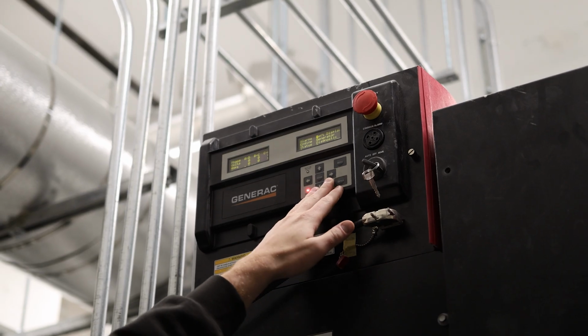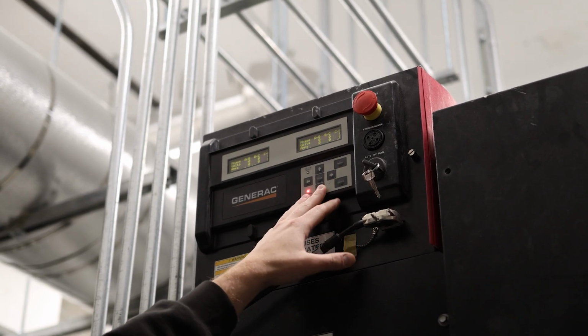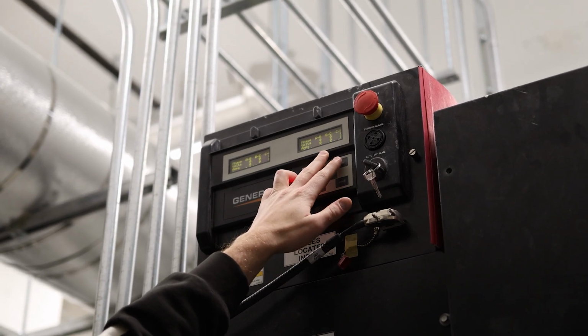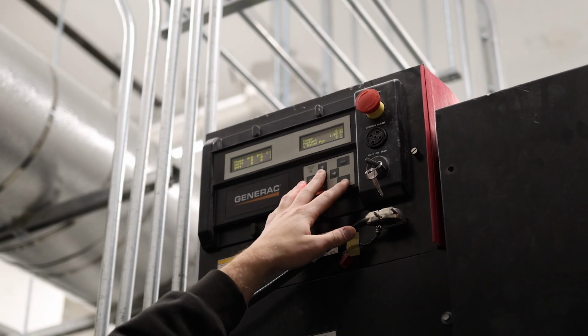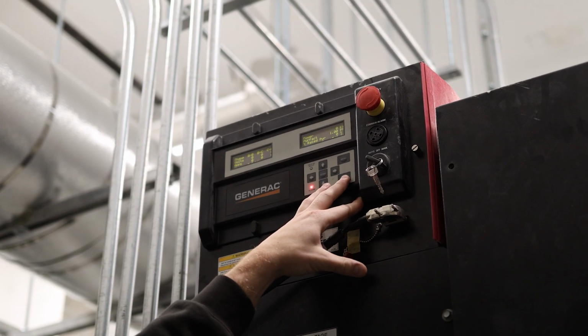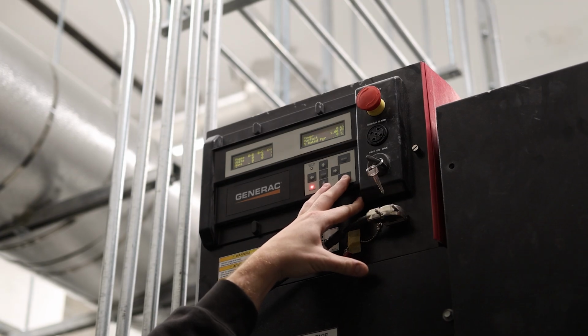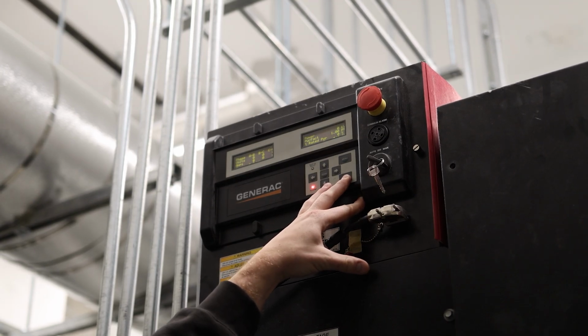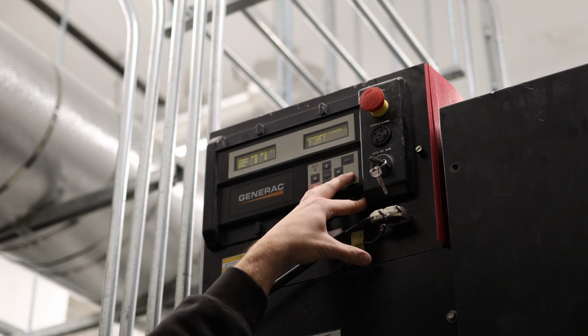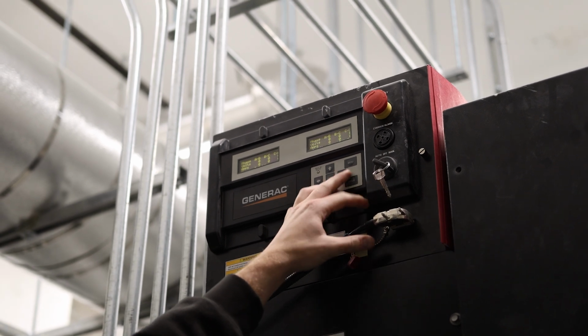Menu. If we go right and down, generator, this is basically our volts page again, but we can cycle through and get a bit more detailed information, mostly for servicing and testing, to see our power factor of the building, our rated power, kilowatts, kVA, all that good stuff.